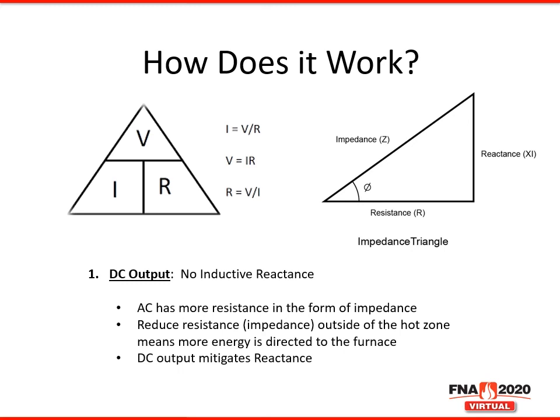Now, let's get into some of the theory of why this is so much more efficient. Let's start with the first point, which is DC output is better. With DC output, there's no inductive reactance. If you look at the triangles here, on the left we have Ohm's law, described visually, and on the right we have the impedance triangle. With AC output, when you consider the impedance triangle, we not only have the resistance of the circuit, but also the additive reactance. Reactance adds more impedance to the circuit, and it is a function of the AC waveform as well as the physical area within the secondary circuit. AC has more resistance in the form of impedance because you have more of that inductive reactance.